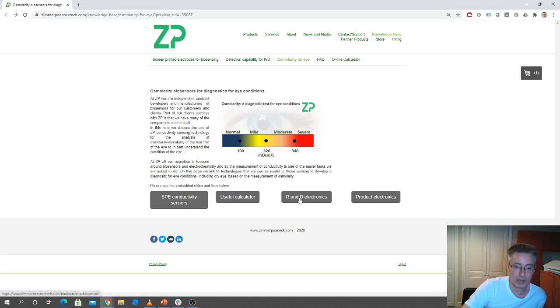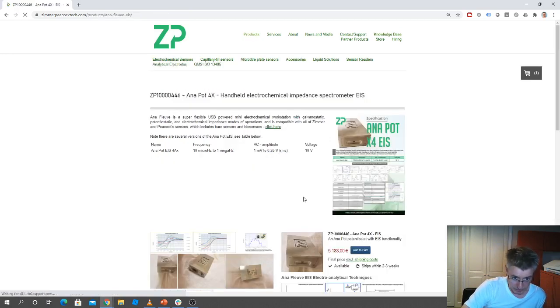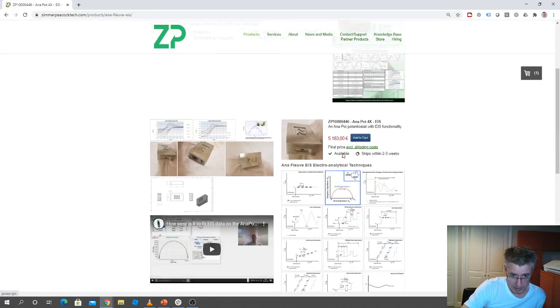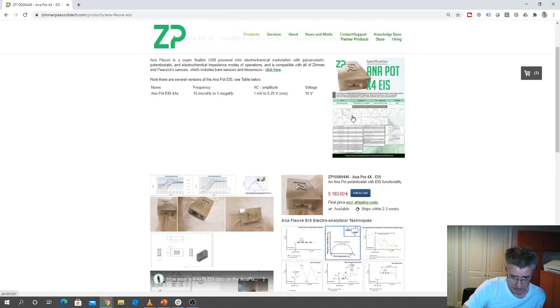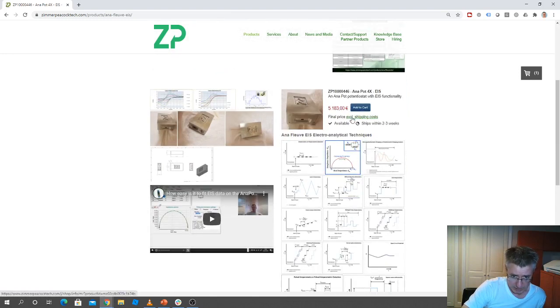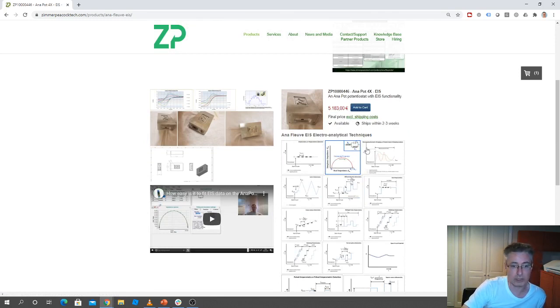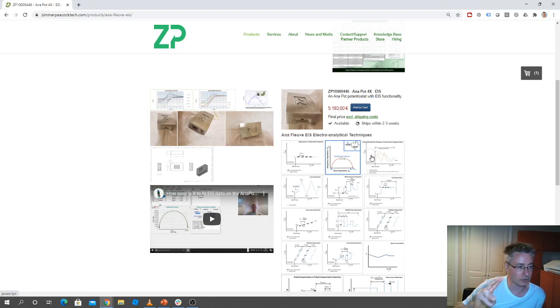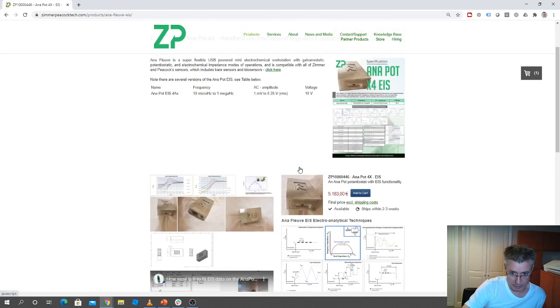When you're in the R&D setting, you're basically trying to measure conductivity, and for that we're recommending an instrument from us called the Anapot EIS. It's an impedance spectrometer, so it's a good way of measuring conductivity between two electrodes, and that's useful for measuring osmolarity. So we do have a piece of hardware for R&D purposes.